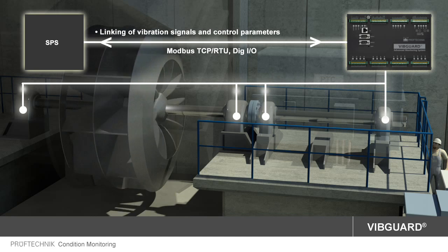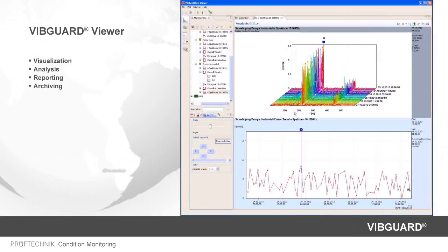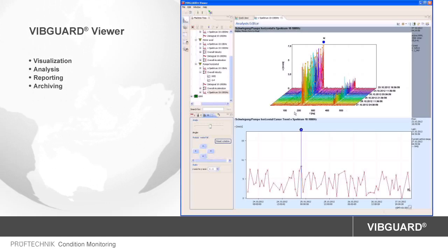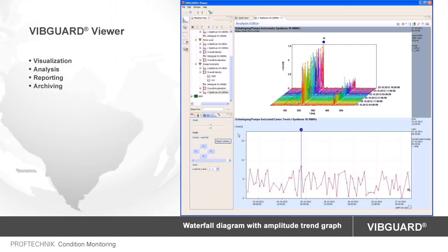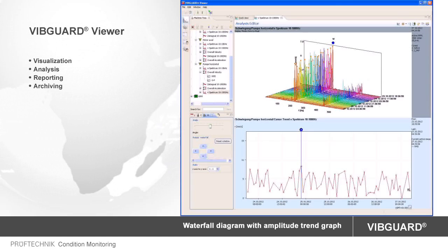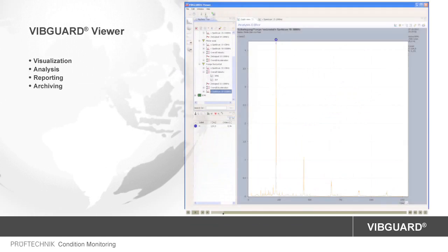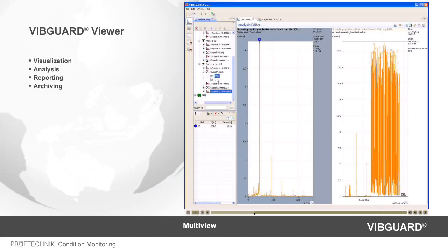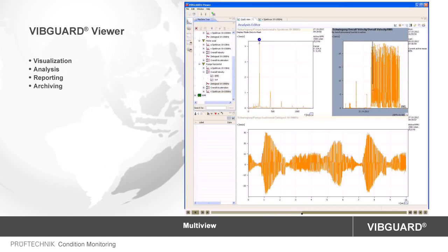A direct time link with the vibration parameters is established. The newly developed software, VIBGUARD Viewer, configures the system and handles the measurement data. In addition to the reporting tool for creating individual event reports, the analysis tool features numerous functions for data analysis and visualization. With the combination of a waterfall diagram and an amplitude trend, you can very clearly visualize and analyze the course of particular frequency ranges. The multi-view function allows combined visualization of the spectrum, trend and time signal, independent of the measurement location.